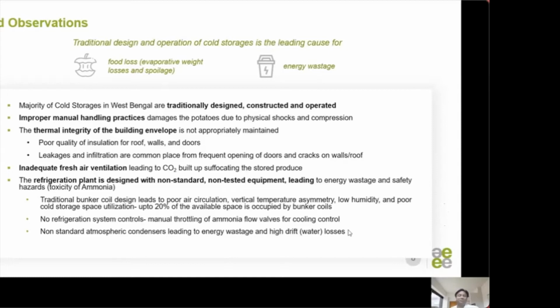The overall refrigeration plant is designed based on non-standard engineering practices, due to non-availability of any standard as well as unawareness amongst the consultants. Automatic temperature-based ammonia flow regulation and isolation valves are not present, which again highlights that the operation is manual. And in almost all the facilities, ammonia safety control valves are absent.